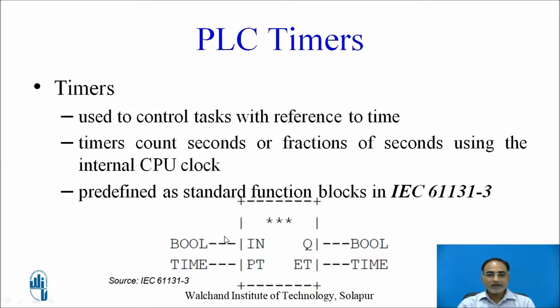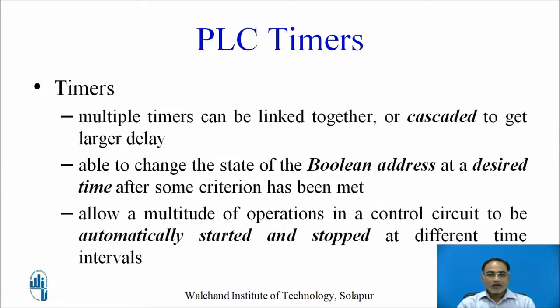A typical timer comes with two inputs and two outputs. Multiple timers can be linked together — also called cascaded together — to get larger delays. Timers are able to change the state of boolean addresses at a desired time after some criteria has been met. Timers allow a multitude of operations in a control circuit to be automatically started and stopped at different time intervals.